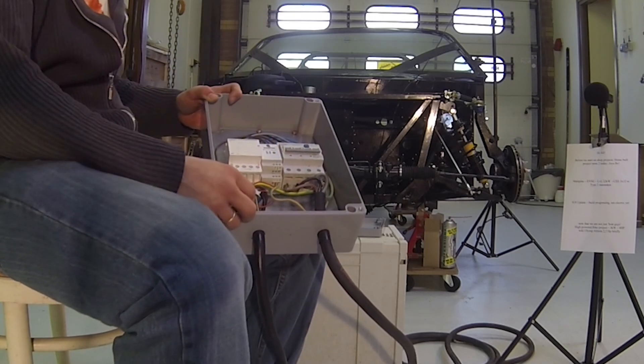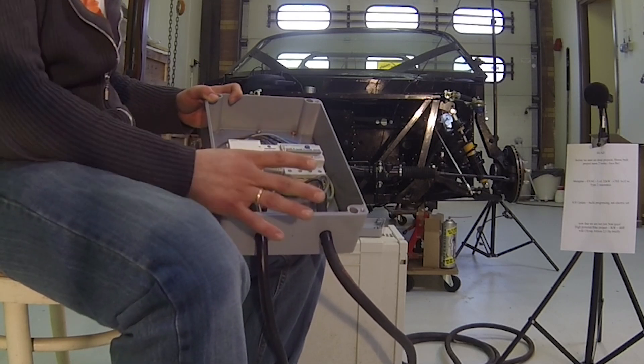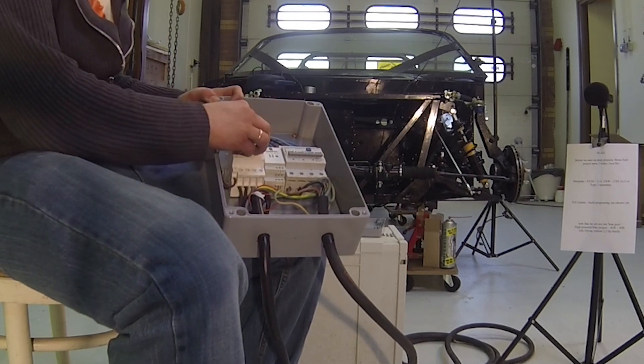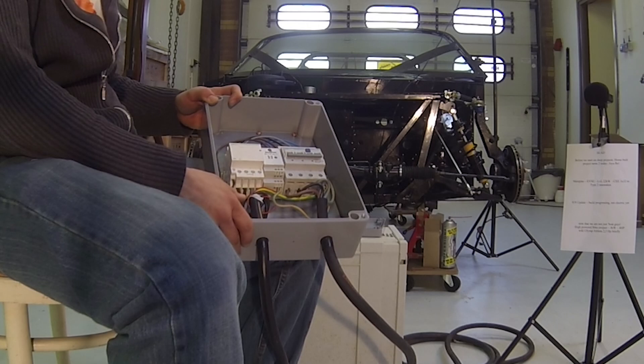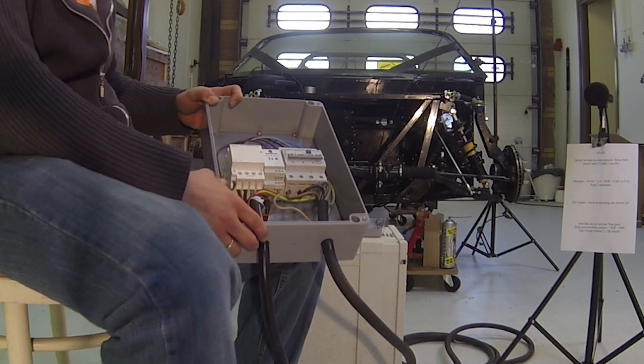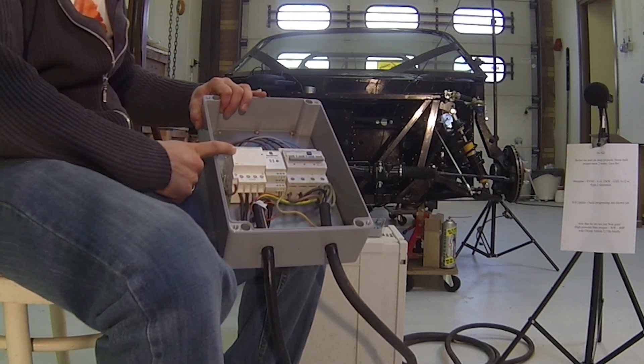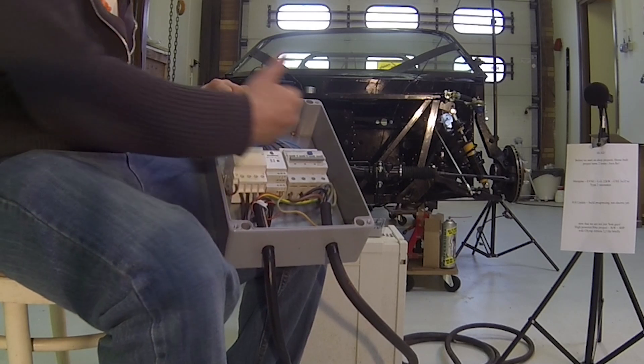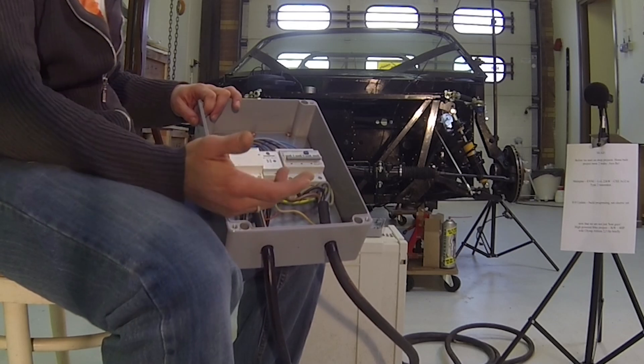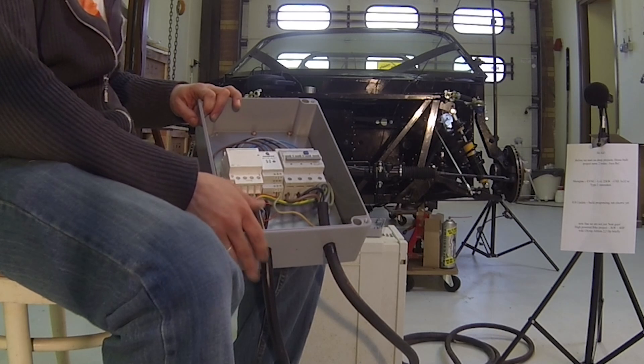After the handshake it's not the unit itself that puts through the power. We have a 40 amp rated contactor on each of the three phases — after the handshake the signal is sent to the contactor, the relay closes giving the power. On the other side we have an RCBO, which in Dutch we call it an aardlekschakelaar, which is essentially a ground fault switch that should save some lives if anything goes wrong.